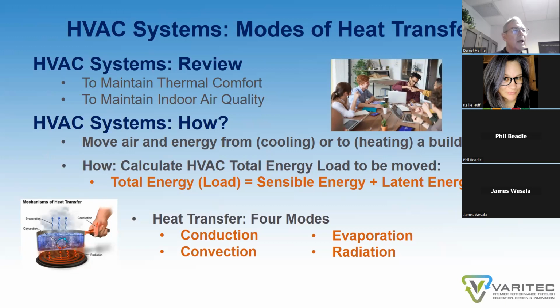So how do we actually condition a building to maintain thermal comfort? Well, we have to calculate the amount of heat load that occurs within the building or leaves the building in winter, and make sure that we remove the energy that's added to the building so we can keep a thermostat at a set point, or how much energy we need to add to a building in winter to keep a thermostat set point. The total energy is comprised of two energy types. One is sensible energy and one is latent energy.